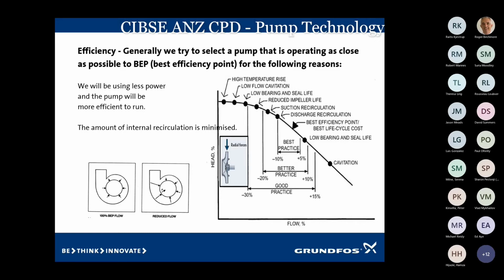And then we go out the other end, we start to get loading on the bearings again. We get a little noise, and then we run into cavitation. And if anybody's heard cavitation, I'm sure some of you have, it sounds like gravel going through the pump. And cavitation, if we leave it long enough, it can really start to cause some issues. We get mechanical seals failing, we get motor bearings failing, and a number of other bits and pieces, which is just weakening the pump. And it's going to cost money. At the same time, it's costing a lot of energy to drive it in those areas.